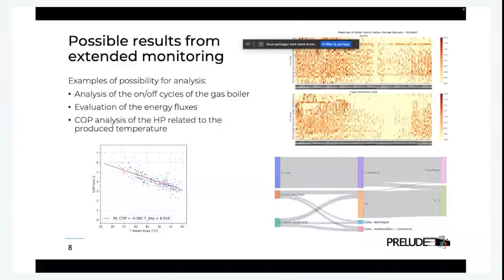Finally, thanks to all the counters we have, we can also analyze the COP of the heat pump related to the departure temperature from the evaporator. You can see that the COP reduces with an increase of departure temperature. So if you ask it for a lower temperature, its COP increases, which is what we expected.